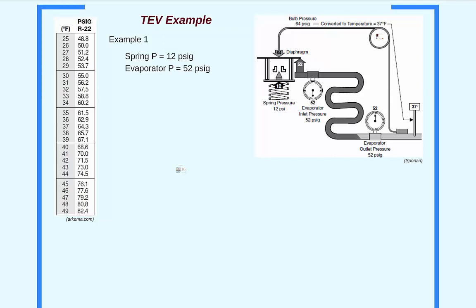In this example, R22 is the system refrigerant running through the evaporator, which is absorbing heat from an interior zone. In this instance, the thermostatic charge is also R22. The spring pressure is set by the manufacturer to be 12 psi gauge, and the evaporator operates at 52 psi gauge.